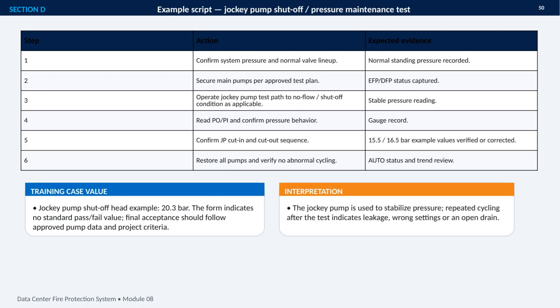This example script walks through a jockey pump shutoff, or pressure maintenance test. The purpose is to verify that the system holds pressure correctly and that the jockey pump responds in the intended sequence. First, I confirm the normal standing pressure and verify the valve lineup. Then, following the approved test plan, I secure the main pumps and capture the electric and diesel fire pump status.